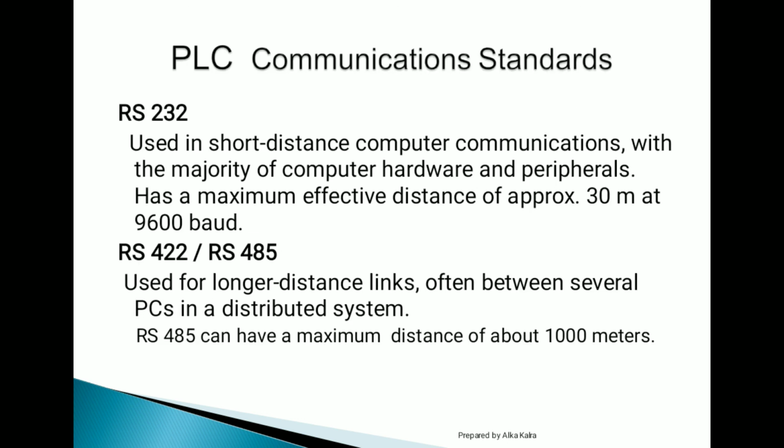How is the PLC connected, and how can various devices be connected to the PLC? For that we have different PLC communication standards. They can be connected through a serial port or a parallel port. For the serial port we use RS232, which is used for short-distance computer communication. Most computer hardware and peripherals can be connected using the RS232 port. It can cover a distance of up to 30 meters, and the baud rate, meaning bits per second that can be transmitted, can be 9600. So this is serial port communication.